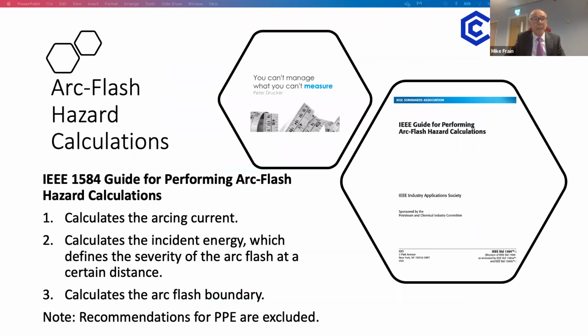So the first item on the agenda: arc flash calculations. Peter Drucker said that you can't manage what you can't measure, and I've felt that's been the case as far as risk assessment has been concerned for quite some time. The IEEE 1584 guide for performing arc flash calculations is probably the most comprehensive means to evaluate the arc flash hazard, and is internationally recognised as an auditable standard. Whilst there are other methods described in my guide, I'll concentrate on the IEEE 1584 for today.